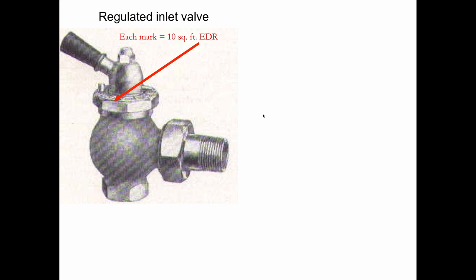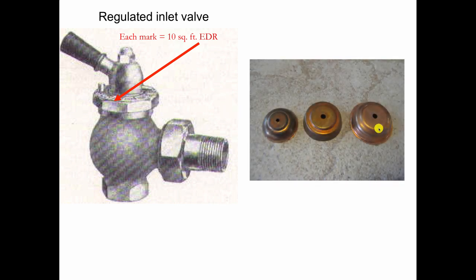So you'll see this type of an inlet valve and you won't see a radiator trap on that radiator. So what you got to be careful about though is if you replace this old style radiator valve on the supply side with a modern radiator valve that's not going to have an orifice in it. And now suddenly you better have a steam trap on there. Otherwise you're going to send steam full bore through the radiator into the return and mess up the whole building. So one way around having to use a radiator trap would be to open this union connection and install an orifice, which is what the old timers did. Often these were handmade. One of them told me that he used to smoke Prince Albert tobacco because it came in a can and he had a punch. And he would punch out his own orifices and use a 10 penny nail to drive a hole through the middle of it, and be able to heat buildings without using steam traps at all, just do it with orifices on the supply side.